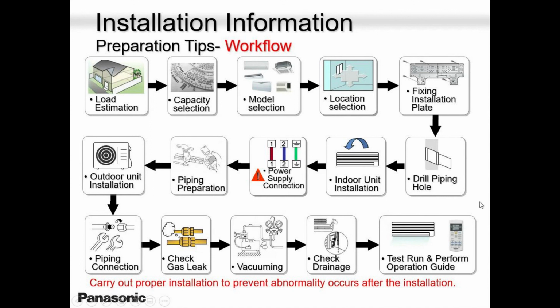Then the outdoor unit location. Outdoor unit location is very important. Sometimes the guys put it in a location where rain falls onto the unit, and then after rain, snow, and you name it. So that's not a good location. It's going to freeze your outdoor unit easily. And then your outdoor unit will be fighting between a frozen coil and de-icing. De-icing or defrost is taking place, but there's so much ice built up due to the location where you installed the outdoor unit. So keep that in mind as well.